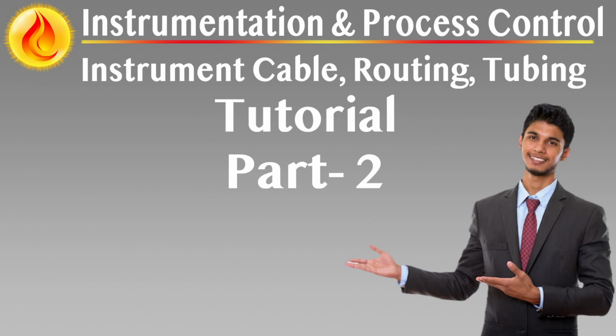Measures must be reviewed and approved during the design phase to ensure coordination with structural lightning protection systems and plant-wide earthing arrangements. Protection for instruments and cabling in protected areas. Wherever possible, instruments and associated cabling should be installed in areas shielded by earthed structural steel or dedicated lightning protection systems. These protected areas reduce the likelihood of direct lightning strikes.